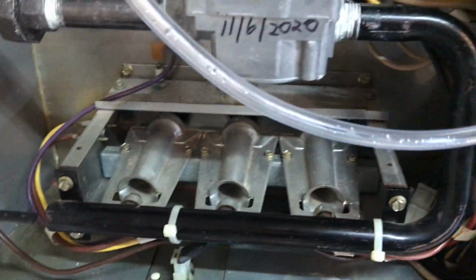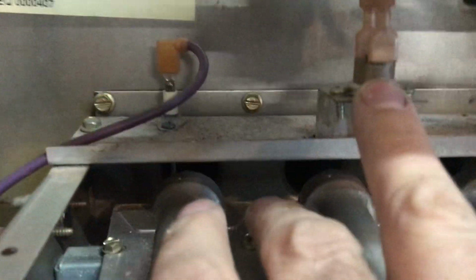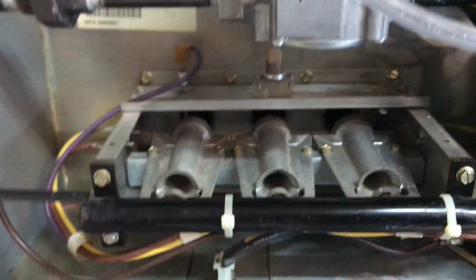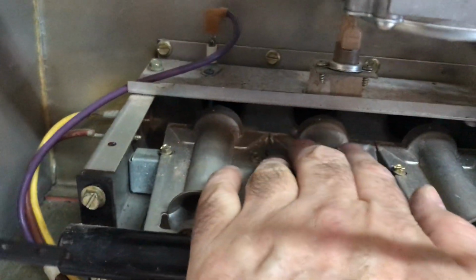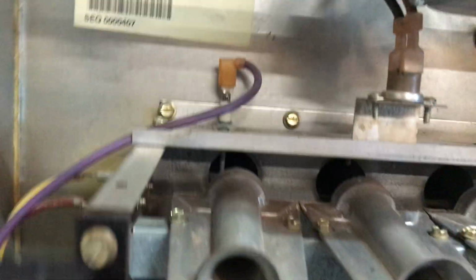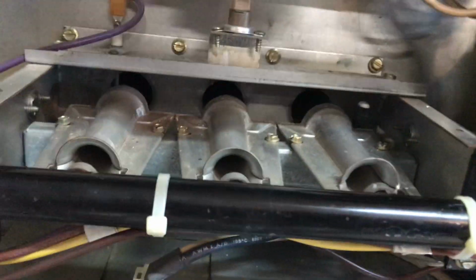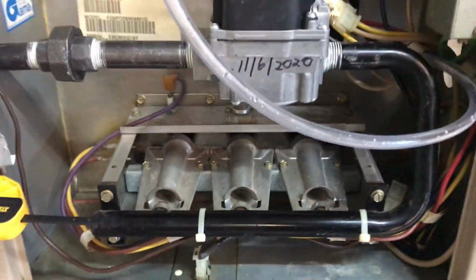Looked it up on the internet, and it said one of the temperature limit switches were open. So with an ohmmeter, I checked them all and found out that this one here was tripping. There's a little push button in the center. You can reset it, and this is just a little localized over temperature sensor right above the burners. My suspicion was that the burners were burning a little bit too hot and creating too much heat in this general vicinity. And the only thing that would cause that would be the pressure being too high.